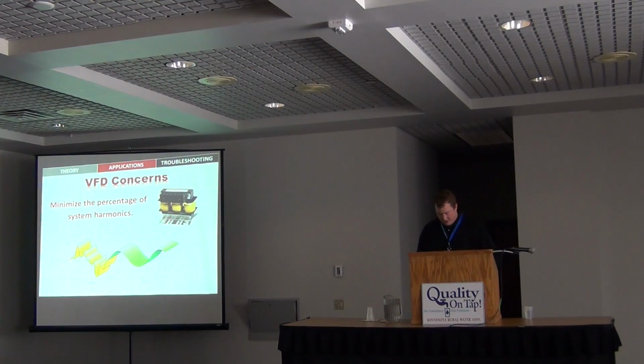What else can we do? We can put on DC bus chokes. That's something that goes on the downstream side of the VFD. There's also something called a harmonic correction unit. Eaton makes one, it's called an HCU, and Square D makes one called an AccuSine. I think there are also some other ones out there from some of the smaller filter companies.